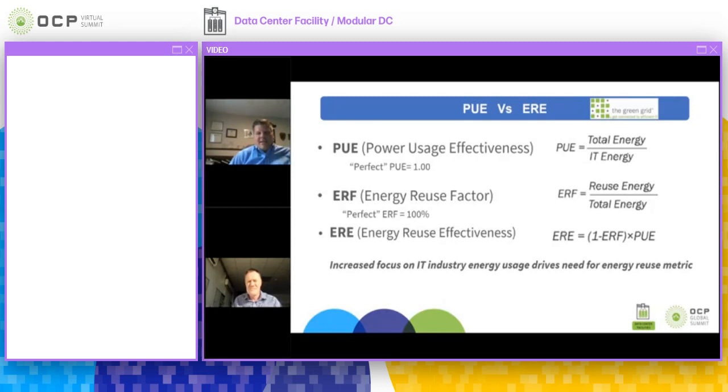One of the things, because I was involved with the Green Grid years ago, I recall the introduction of power usage effectiveness. At the time, there was no intent that it included energy reuse; there was a separate category called energy reuse effectiveness. And so, is it possible to get a PUE of less than one? Absolutely not.